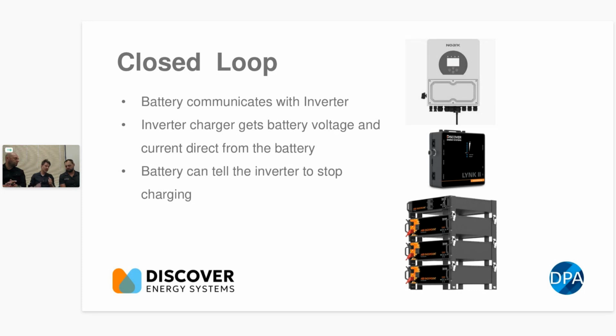Does that also mean that as the battery ages and the state of health goes down, the charging algorithm is going to respond to that? Yeah, the key to closed loop is that we're able to look at the cell voltages of each individual battery within an entire system. If you've got multiple packs with multiple cells in each, we're able to look at the cell value. When we do dynamic voltage, if any of the cells are diverging, we can start to pull the voltage down, which allows us to reduce the current because of Ohm's law, and allows us to top-balance effectively at a relatively high current. So it allows us to manipulate the system quite well, and to not only balance cells but balance packs.